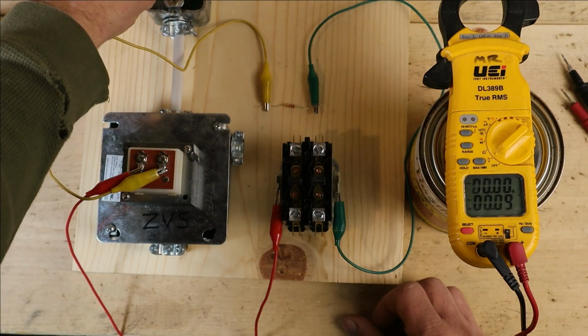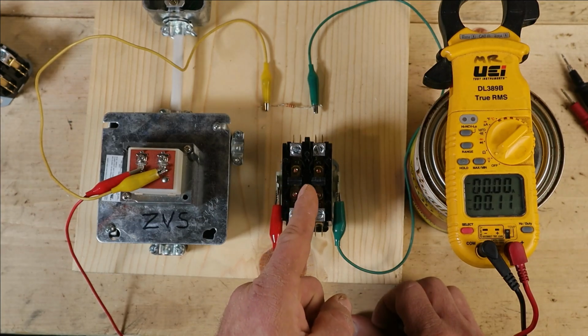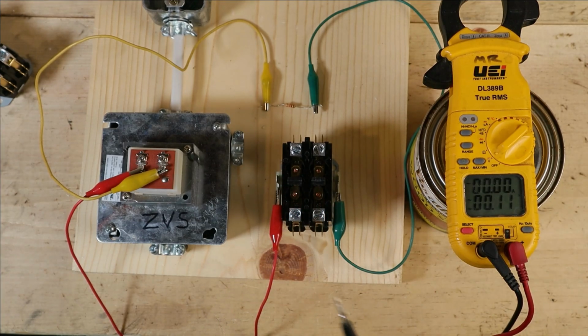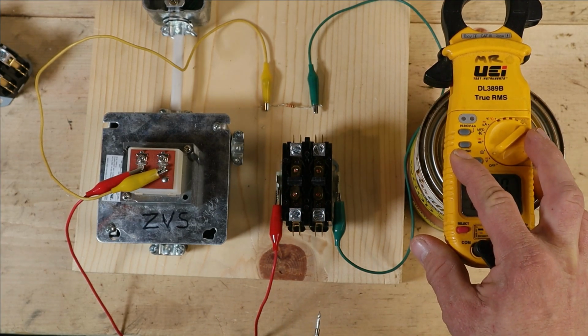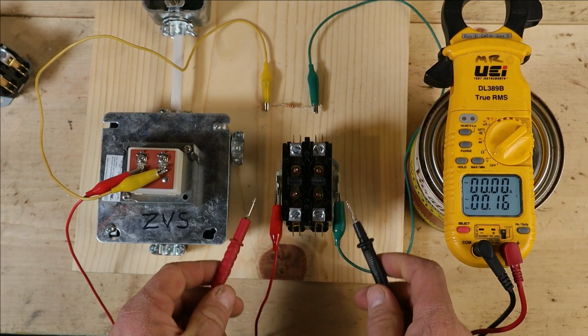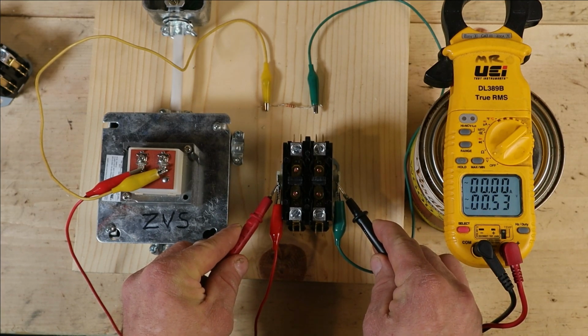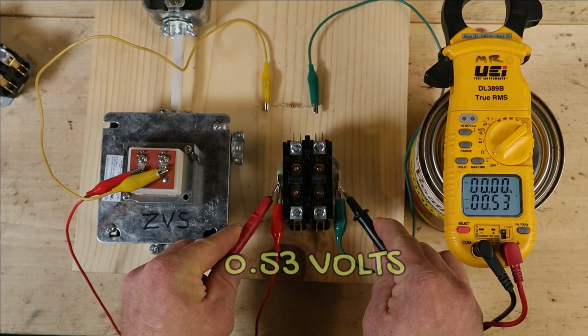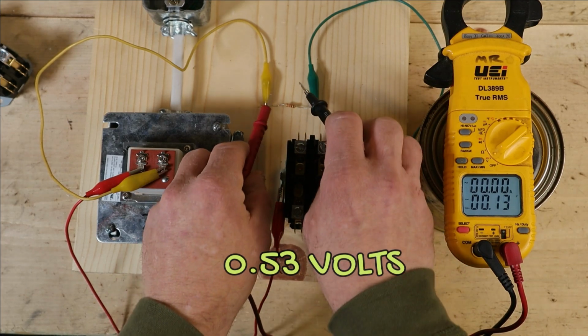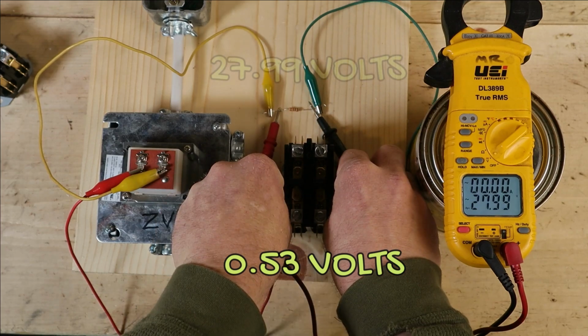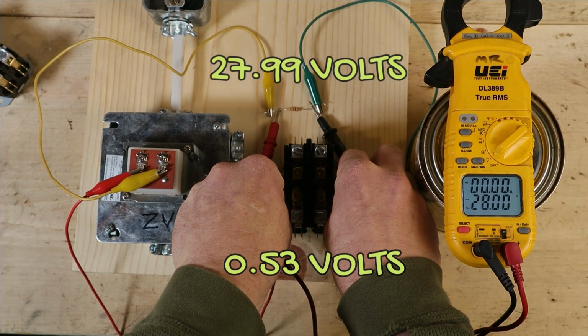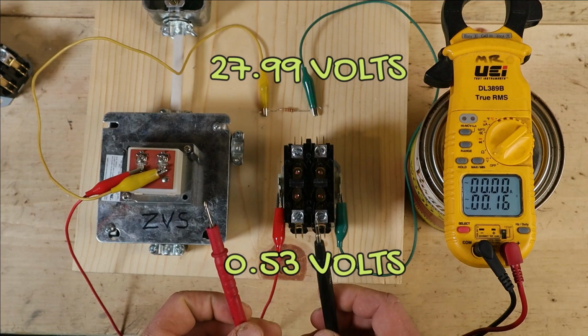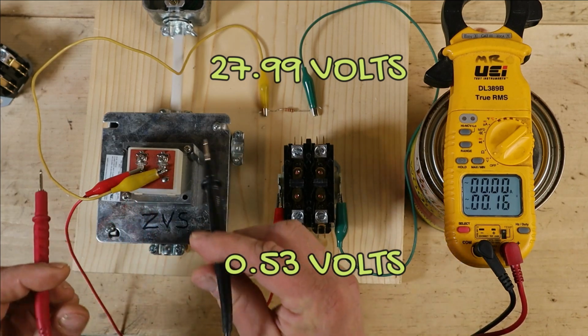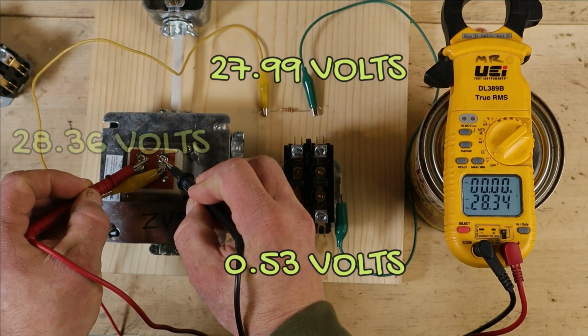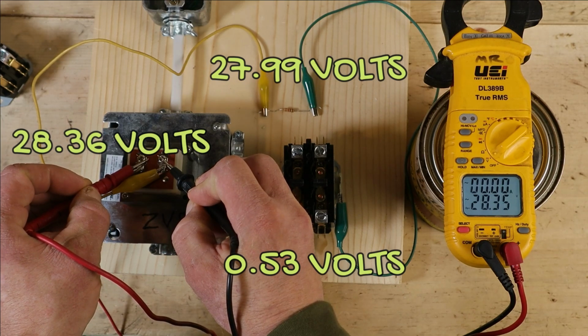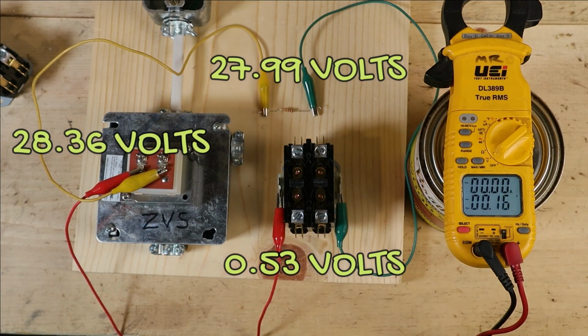Now let's go ahead and turn our power on, and you can see our contactor didn't pull in. So if we were to take our multimeter, put it in voltage, and do a voltage reading across this coil, you could see we're only reading about half a volt there. Now if we did the same thing on the resistor, you can see we're reading 28 volts there. So right now we should be reading about 28.5 off of this transformer. And 28.36, pretty close. So what's happening here?